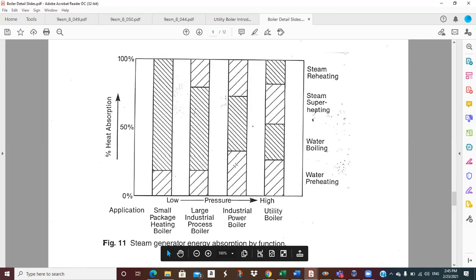An industrial power boiler is the same situation, but we're going to put more into superheating because we're going up to a higher pressure and a higher temperature because we want to generate some electricity. This would be a cogen situation where you're generating power and then taking that thermal energy to a process load to make a widget or cook some soup or whatever. Then a utility boiler: these first three are pretty much the same. We have to heat up to the saturation temperature for our boiler pressure, boil it, and superheat it. And then, by gosh, after it goes through the first turbine, we're going to bring it back and reheat it again. So it just shows the distribution of where the energy is used, a comparison based on the type of boiler. That's kind of interesting. Okay, that's enough.